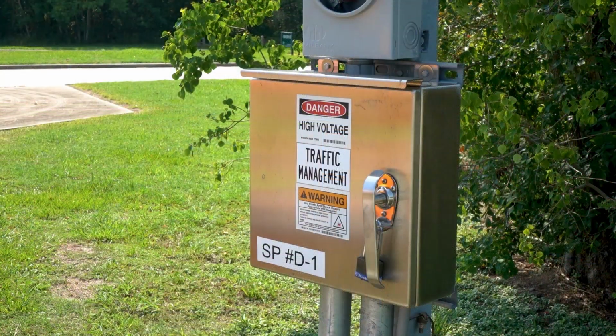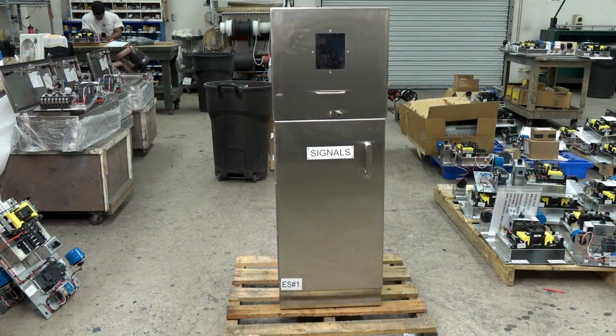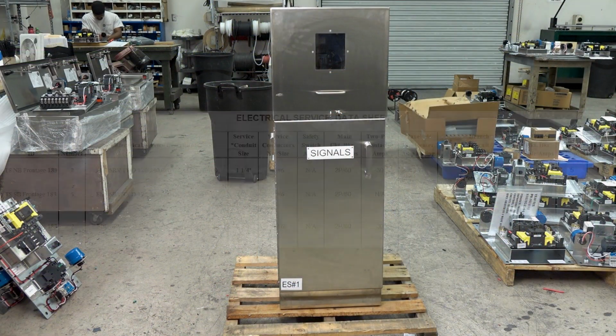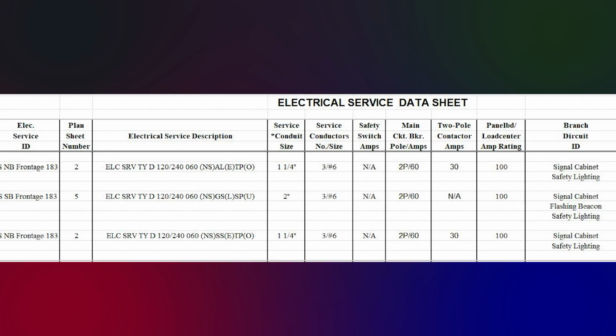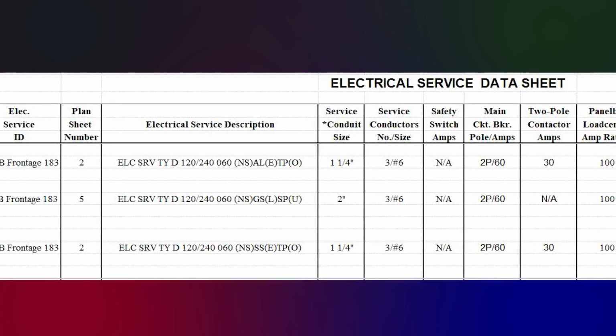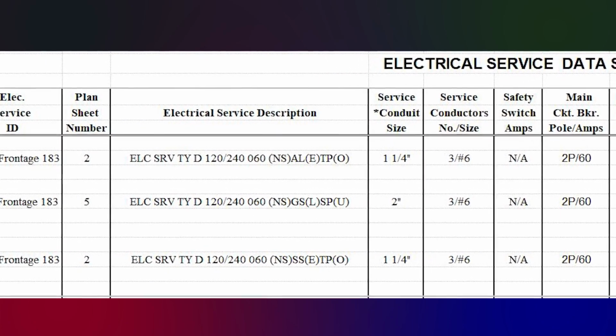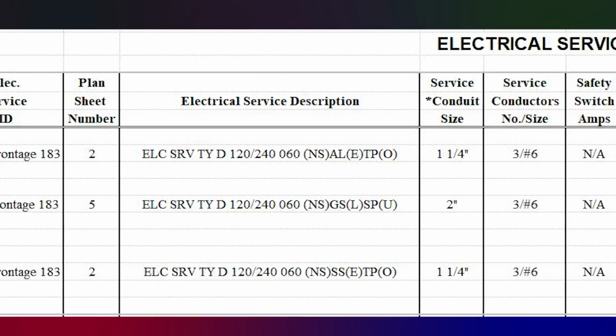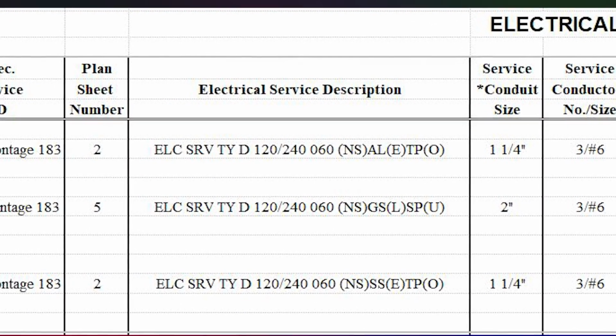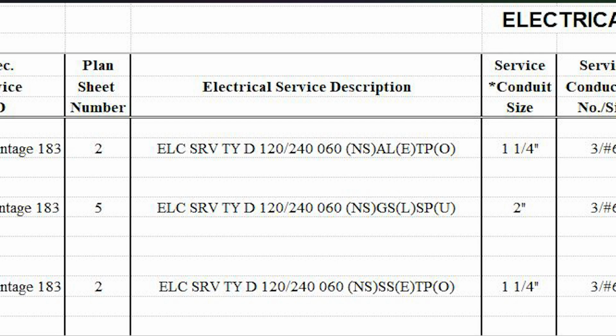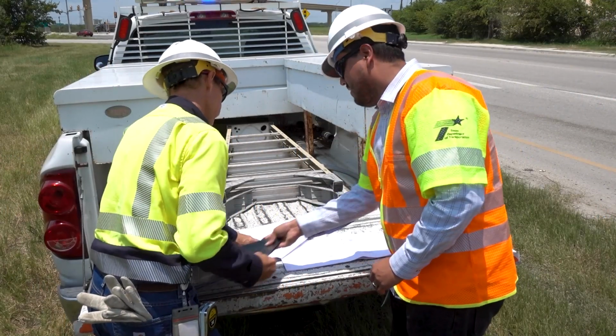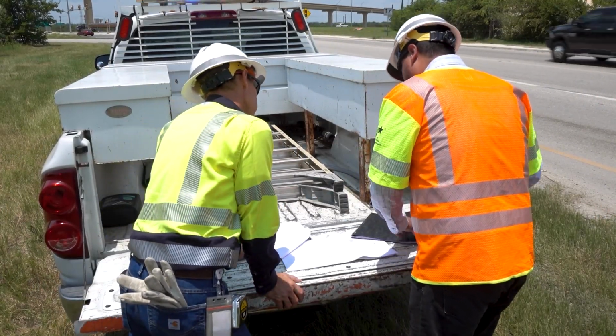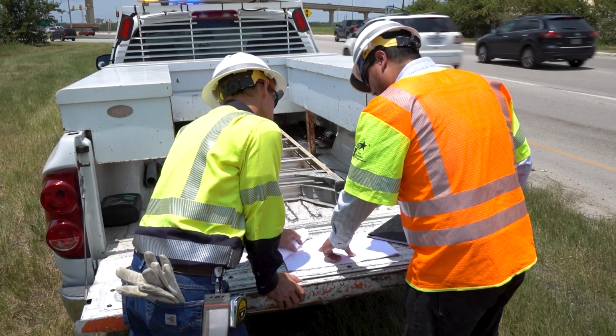With our review of how a service works now completed, let's address inspection of a Type D electrical service in more detail. For each job and location, the engineer has designed a specific type and size of service, the details of which are described by each service's descriptive code. The inspector must consult the job's plan sheets to find the data specific to that individual service. Service data can be located on the electrical service data chart and other pages of the job's plans.